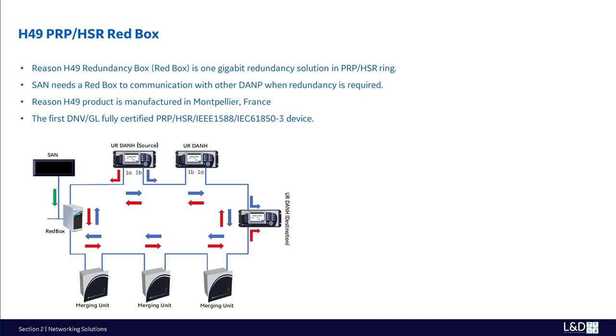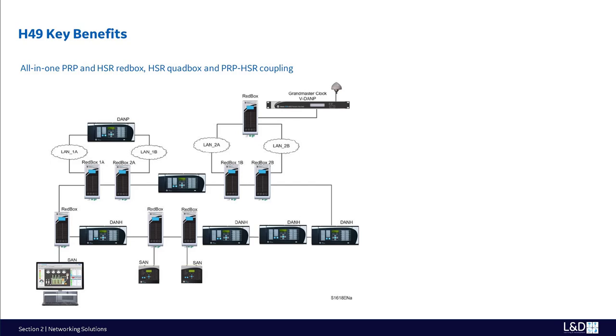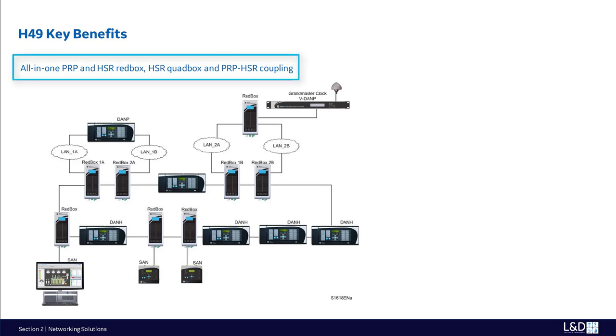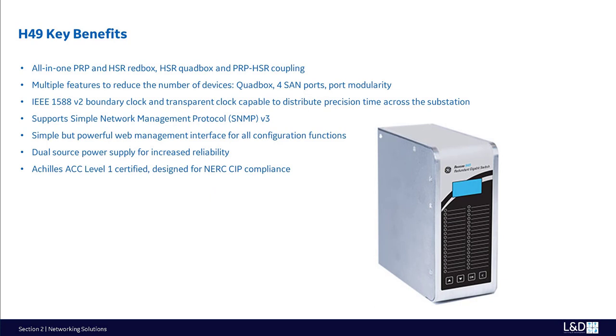The Reason H49 product is manufactured in Montpellier, France, and is the first DNV GL fully certified PRP HSR IEEE 1588 IEC 61850-3 device in the world. H49 has these key benefits: all-in-one PRP and HSR Red Box, HSR Quad Box, and PRP HSR Coupling Box. Multiple features reduce the number of devices: Quad Box, 4 SAN ports, port modularity, up to 4 SAN ports to connect PRP HSR non-compliant devices to the redundant network, reducing the number of Red Boxes. 3 available SAN ports can be used as a PRP HSR coupling box.